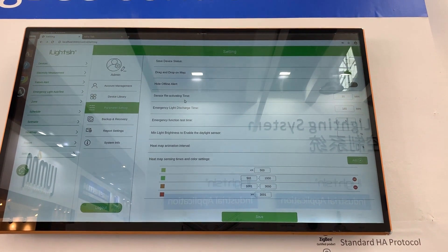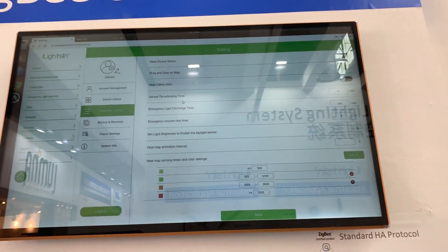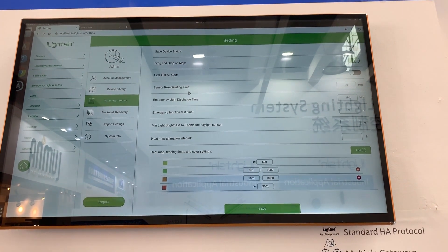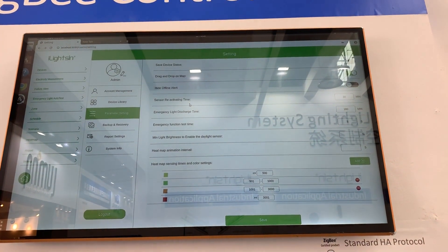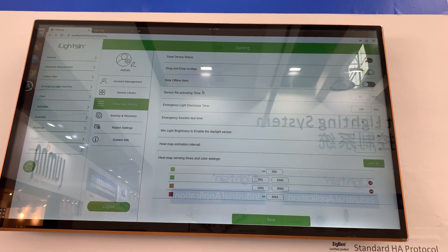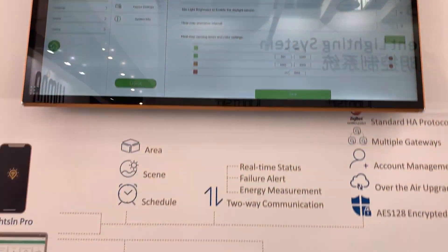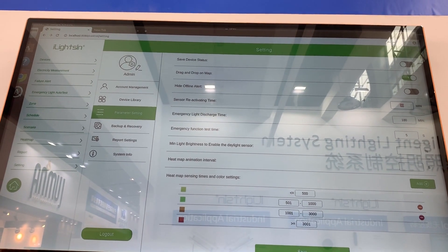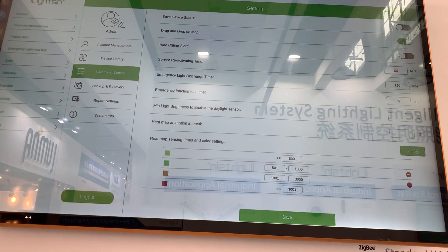Hide offline alert. Sensor reactivating time is important if you have motion sensor or light sensor control. Our system listens to the last command, so even if the device is under sensor control, if we use a remote control to control the lights, the sensor will no longer activate after that. So we need to set the right time here to ask the sensor to take control again later on.